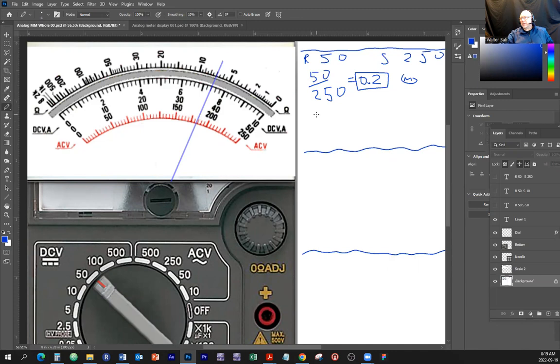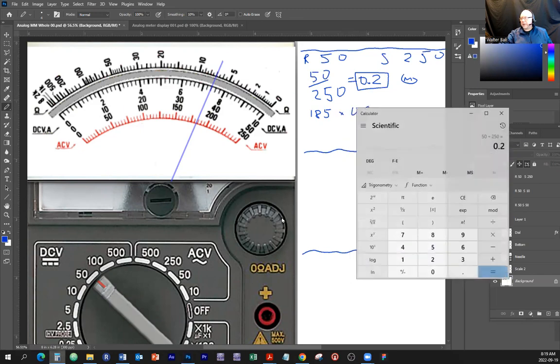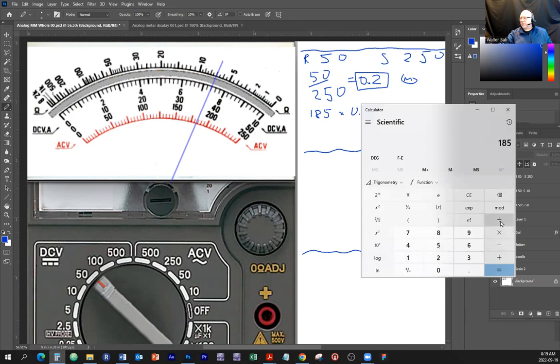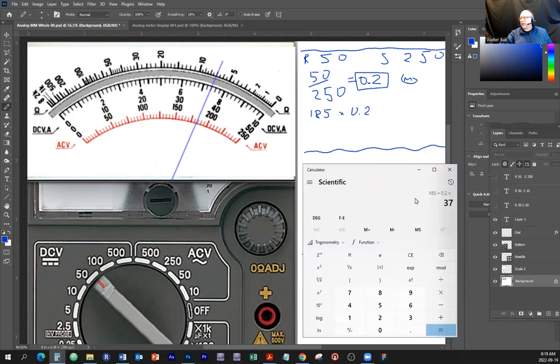So let's take 185 as the reading, and we're going to multiply it, this is our multiplier, by 0.2. Let's see: 185 times 0.2. Oh look, it gives you the same reading as 37 volts. Of course it's going to give you this same reading.